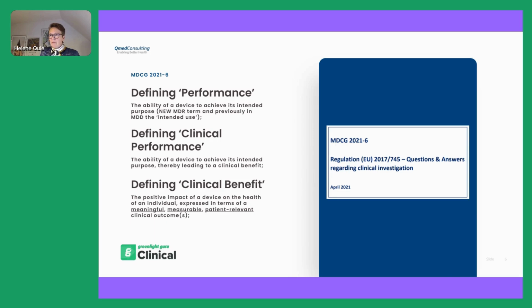So when we walk through the different definitions of relevance for this topic, we need to talk about performance, clinical performance, and clinical benefits. In accordance with the MDR and relevant MDCG guidelines, the performance of a device is the device's ability to achieve its intended purpose as stated by the manufacturer. And extending that into clinical performance, it's the medical device's ability to achieve its intended purpose and thereby lead to a clinical benefit when it's used as intended. And the clinical benefit means the positive impact of a device on the health of an individual. And it's expressed in, this is very important, a meaningful, measurable, and also patient-relevant clinical outcome. And that includes outcomes related to the diagnosis or positive impact on patient management or public health.